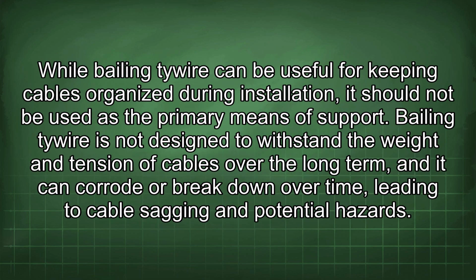While baling tie wire can be useful for keeping cables organized during installation, it should not be used as the primary means of support. Baling tie wire is not designed to withstand the weight and tension of cables over the long term, and it can corrode or break down over time, leading to cable sagging and potential hazards.